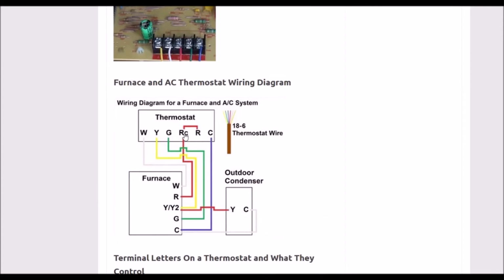Sometimes R and RC are tied together, and sometimes they're not. On a 4-wire system, sometimes they're tied together like this. It's basically just sending the 24 volts to both of them, since they both are 24 volts. 5-wire systems will often be separate, so it just varies. However your system's set up, just use that. But basically, you'll have 24 volts AC coming in on the R's, and on the C is going to be the common wire coming from the transformer.